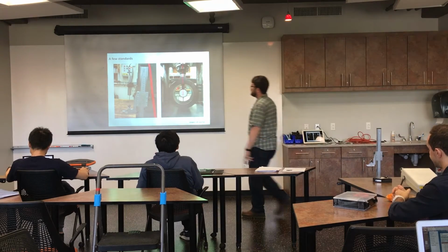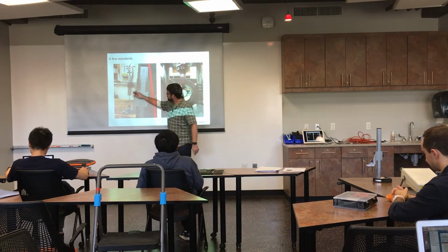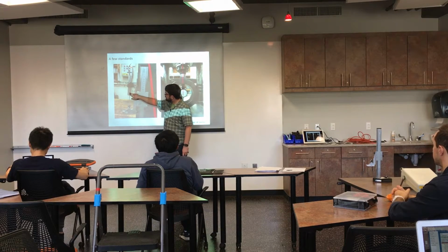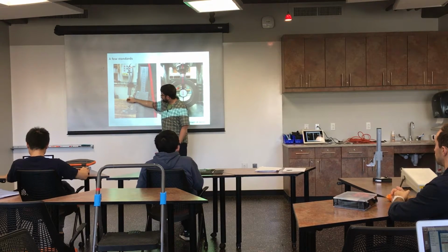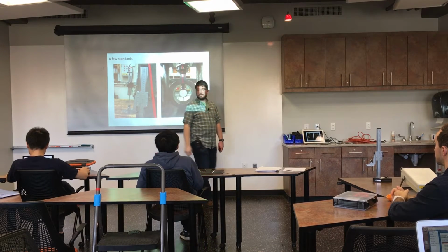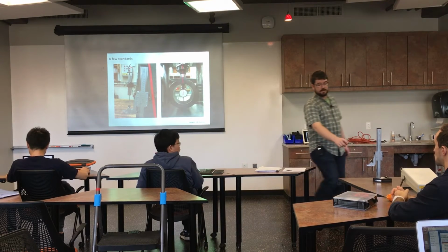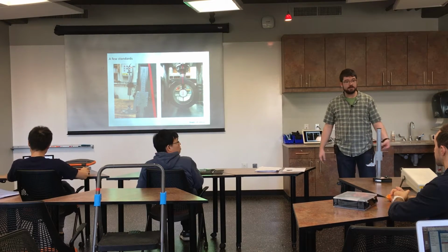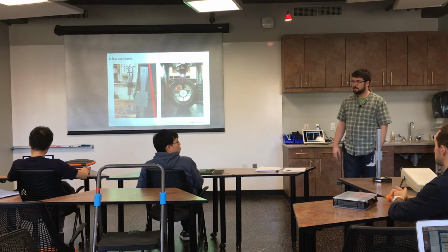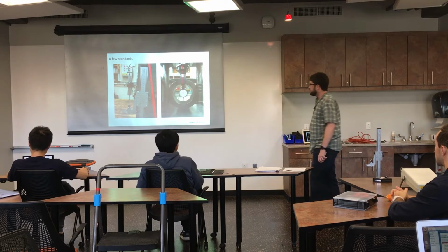All right, so here's the vernier. You'll see you have your displacement transducer affixed on a ring stand, which we've got over there. You put the core of the transducer onto that vernier right here, and then you'll move this in 1 millimeter increments, or you could do it in 0.5 millimeter increments if you wanted to, and get your calibration data set.